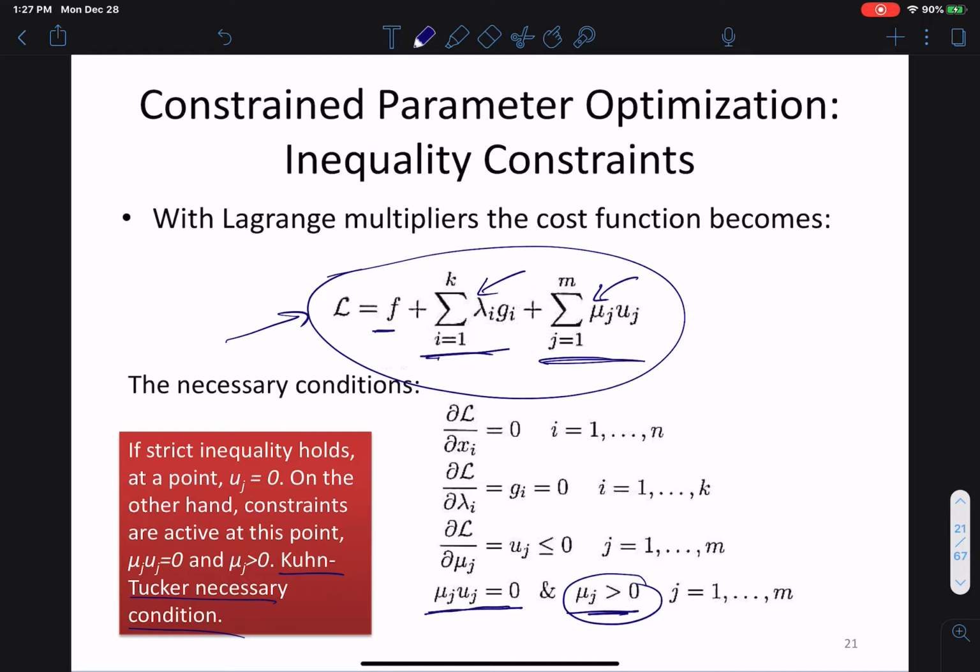What it's basically saying is that when you hit one of the limits, let's say while solving your optimization problem in the first two or three rounds, or the first round, you hit a limit for the power plant I just showed you. For one power plant the limit was 1,000, but the solution was 1,100, so you hit the 1,000 limit. So what you do is set the upper limit now, so PI would not change anymore. It would be out of the optimization problem now. You just set it to 1,000 megawatts. In plain terms, that's what the necessary condition is saying.